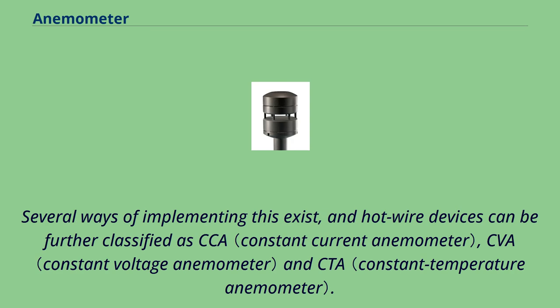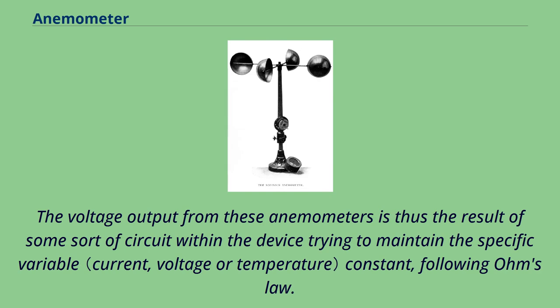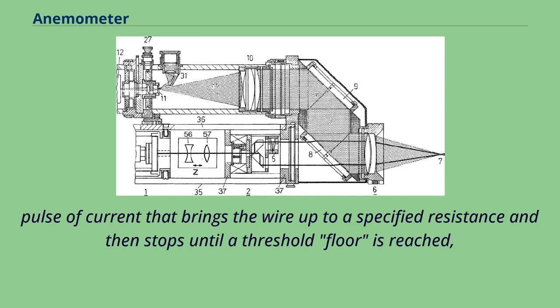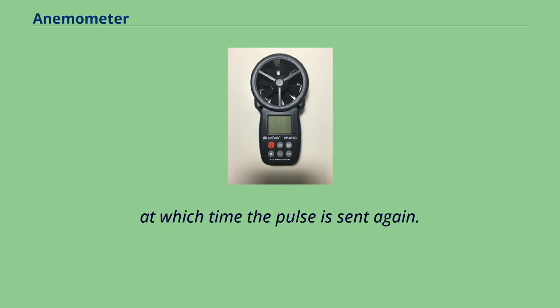Several ways of implementing this exist, and hot-wire devices can be further classified as CCA, CVA, and CTA. The voltage output from these anemometers is thus the result of some sort of circuit within the device trying to maintain the specific variable constant, following Ohm's law. Additionally, PWM anemometers are also used, wherein the velocity is inferred by the time length of a repeating pulse of current that brings the wire up to a specified resistance and then stops until a threshold floor is reached, at which time the pulse is sent again.